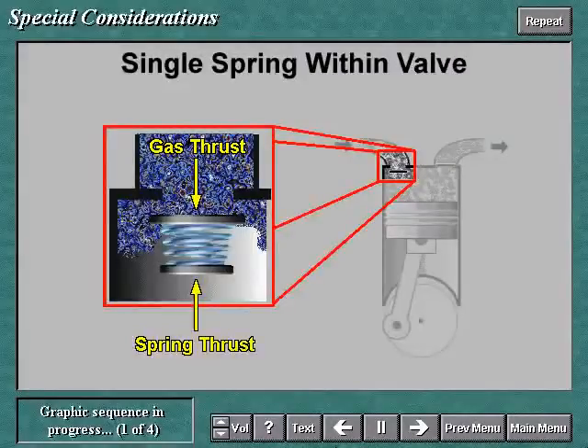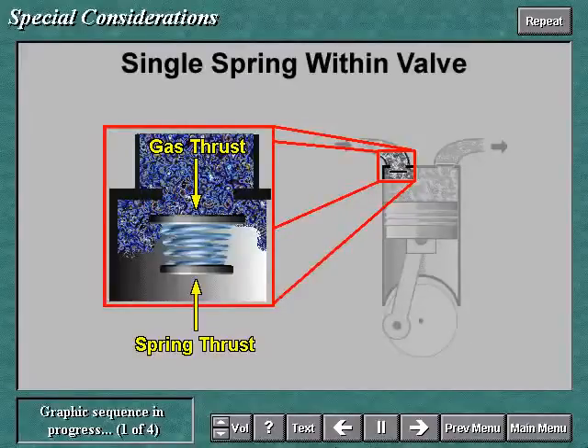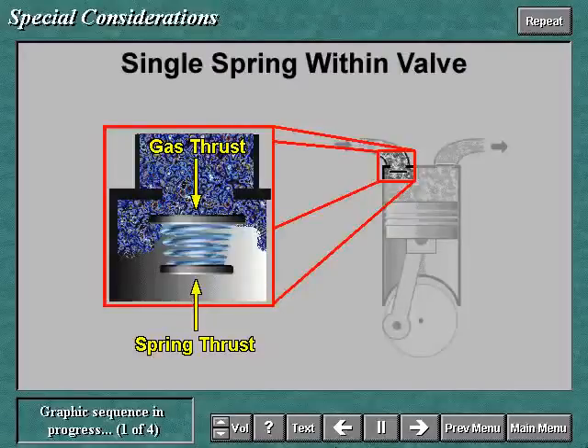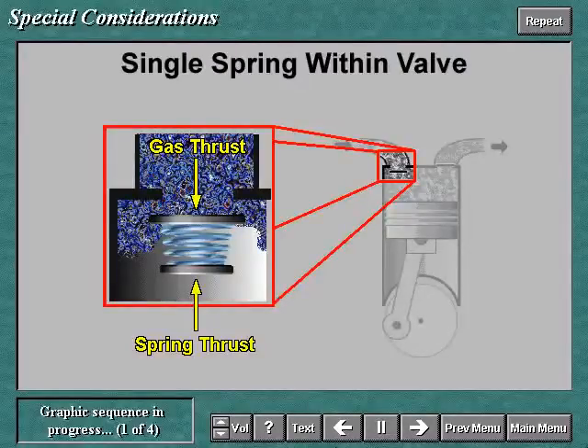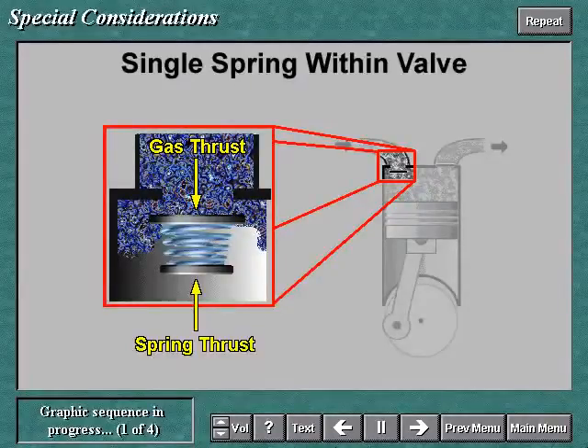The valve rings are kept lifted by the drag force due to the gas flow. They remain lifted as long as this force is stronger than the opposing force of the springs. The valve, however, must close just at the end of the stroke, whether it is a suction or discharge valve. If spring stiffness and ring lift or gas velocity are not correctly related to each other, the rings are not stable and will flutter.